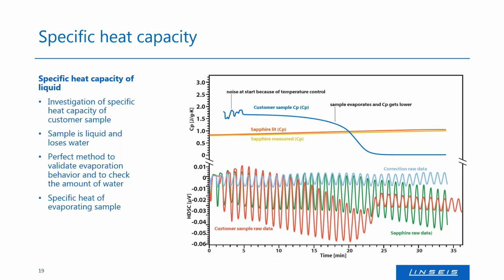What we also can see here is that the amplitude of this signal gets lower and lower until 23 minutes. And if we evaluate this signal, we will see that the CP gets lower here. Of course, the CP of the material inside isn't lower, but the CP the chip DSC, or the device itself, sees is lower because the water evaporates. There's no heat needed to heat it up because it's gone. Basically this was what the customer wanted to see, so he wasn't interested in the difference. Of course, if you want to get the CP of the part when the water is gone, then you have to weigh this crucible again, and then you can calculate the CP after the evaporation of the water.